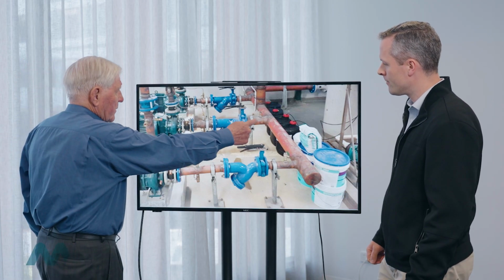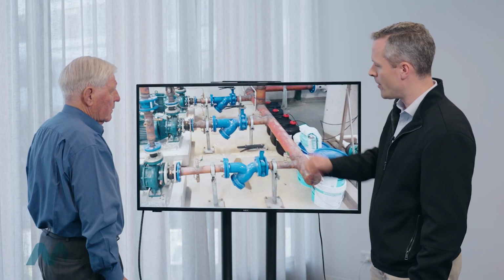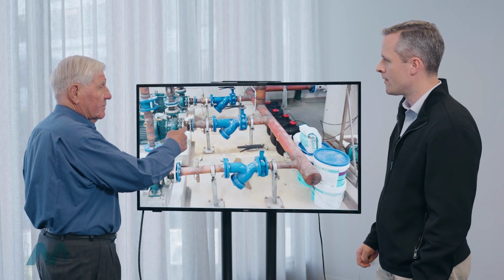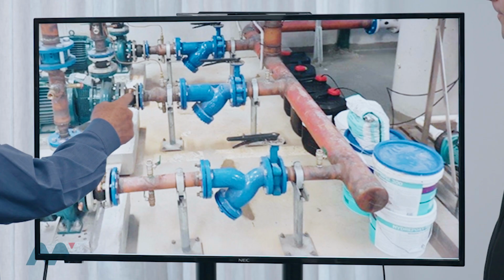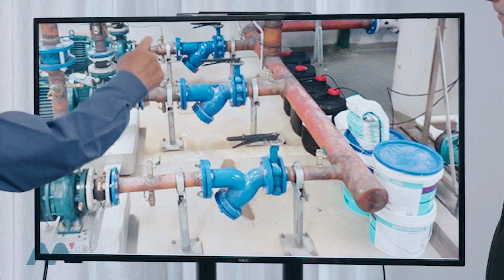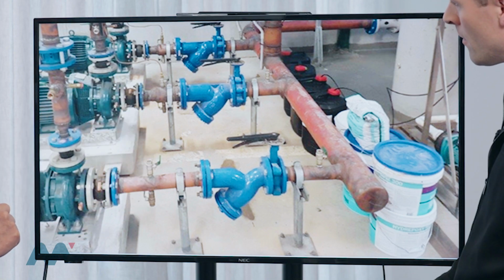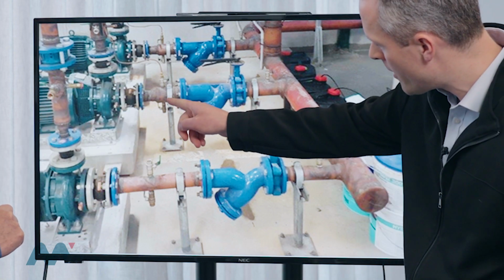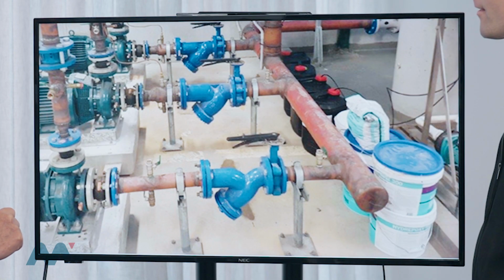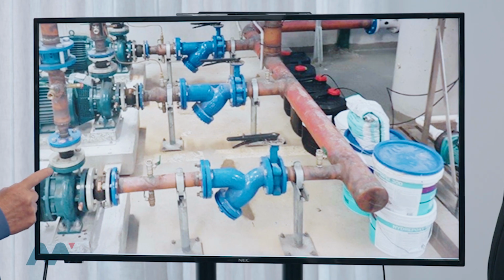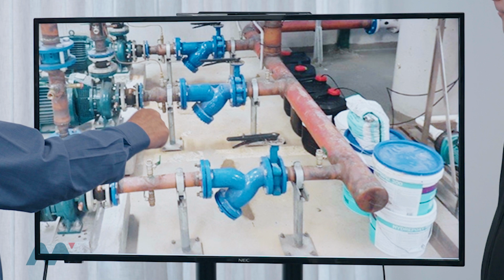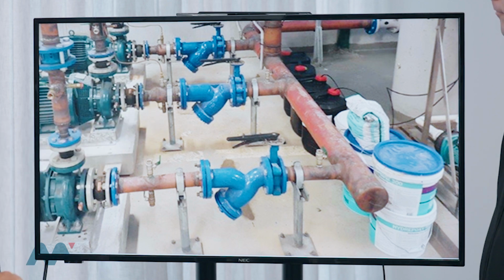What's the size of this pipe? This was 100 millimetre, so going into 80? Yes. So, okay, you need an eccentric reducer at these connections. Otherwise, you're going to get trapped here. I see what you mean. You mean that's not an eccentric reducer? No, that's not an eccentric reducer. That is a concentric reducer. An eccentric reducer has a flat top and a sloping edge to match the pipe diameters.